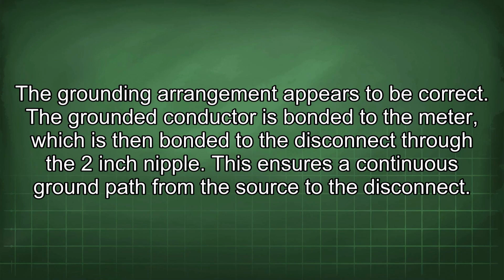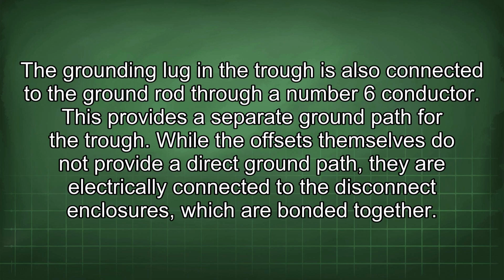The grounding arrangement appears to be correct. The grounded conductor is bonded to the meter, which is then bonded to the disconnect through the 2-inch nipple. It ensures a continuous ground path from the source to the disconnect. The grounding lug in the trough is also connected to the ground rod through a number 6 conductor. This provides a separate ground path for the trough.